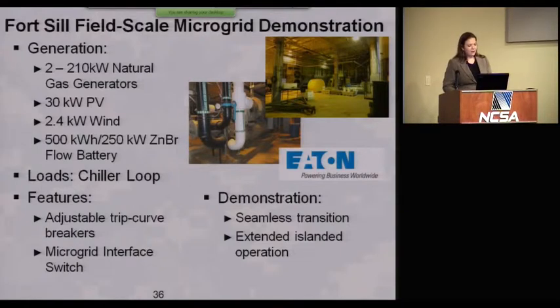It's interesting to think about the power systems protection issues we have in a microgrid. We just disconnected from the utility—suddenly our short circuit current values have changed, our load flow has changed, and that means our relay and coordination settings on our breakers may need to change too. That's part of these adjustable trip curve breakers. Then the interface switch for synchronizing back to the grid, making sure we don't backfeed the grid with our generation, is an interesting technology being developed.